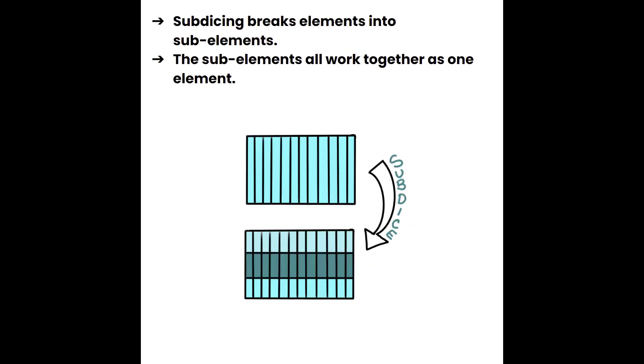Subdicing is the other technique to reduce grating lobes. It breaks elements into sub-elements that all work together as one element. So if a transducer has 12 elements and 12 wires, subdicing physically divides each element into smaller pieces — but it remains 12 wires, not 36, because all sub-elements within one element are still electrically connected to that one wire and act as one element. The different physical cut of the elements changes the interaction of the sound waves produced, thus reducing grating lobes.